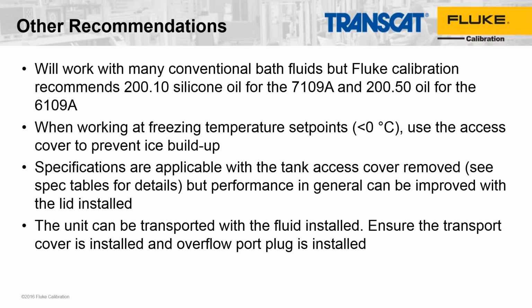We get a lot of questions about what are the fluids that can be used with these baths, and we recommend the 200.10 silicone oil for the 7109A and 200.50 oil for the 6109A. These are the oils that we use in the factory and service centers to calibrate these baths.